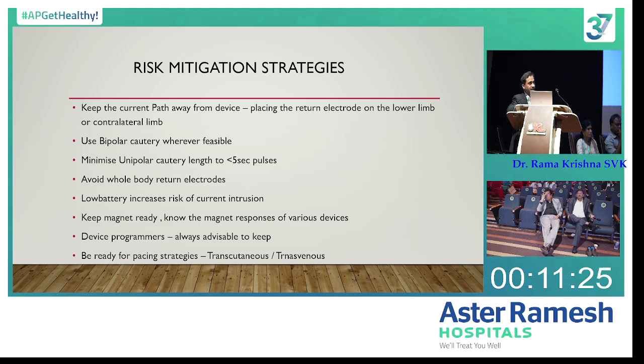Apart from the programming of the devices, there are certain strategies that we have to use to prevent electromagnetic interference. When you are using a cautery, keep the current path as far from the device as possible, at least 15 centimeters away. Use bipolar cautery whenever it is feasible. Whenever you're using unipolar cautery, limit to pulses of less than 5 seconds. Avoid whole body return electrodes. Let me emphasize this: a device with a low battery increases the risk of current intrusion and the risk of electromagnetic interference. Keep the magnet ready and know the magnet response of various devices and various companies also.